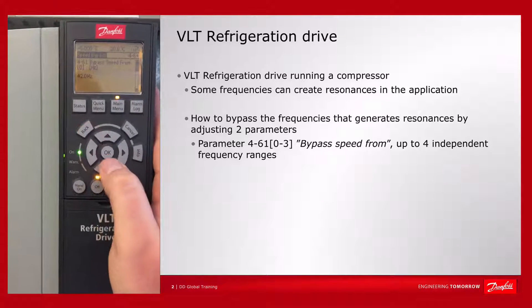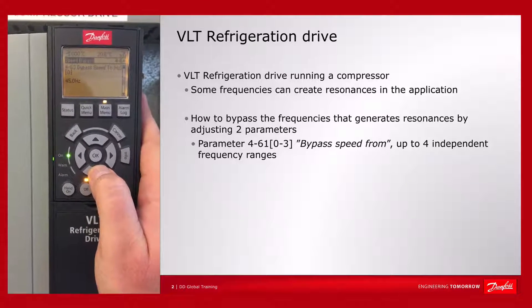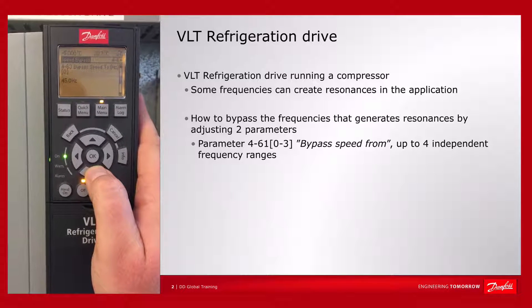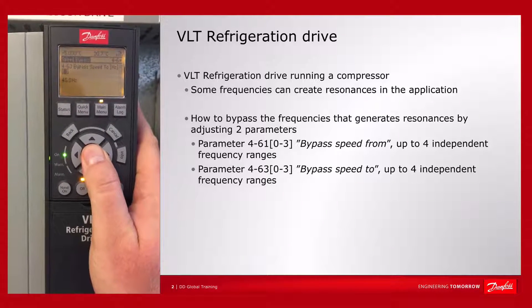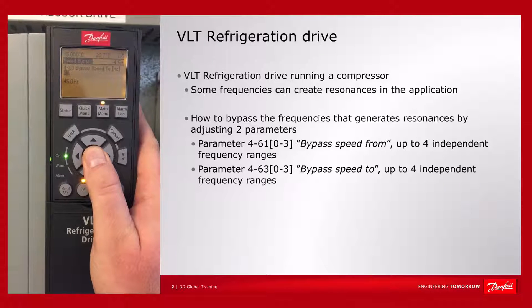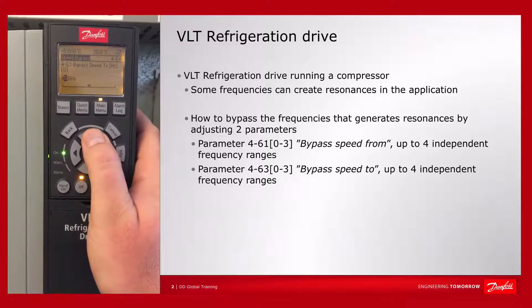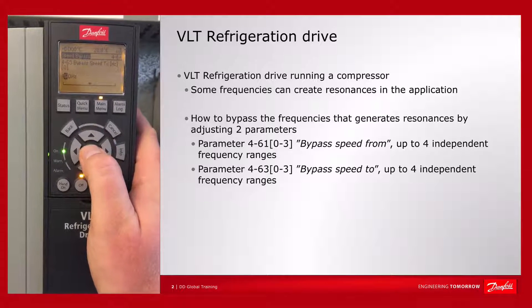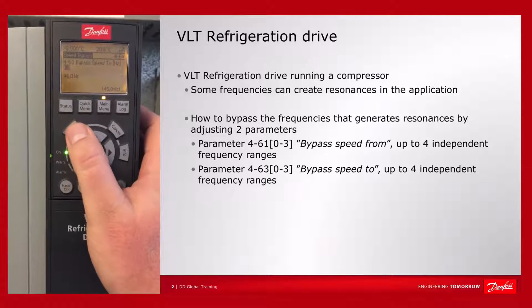Press back, then go down and program parameter 4-63. Make sure it's still on band 0, and we want to skip the band up to 46 Hz. Press OK and press back.